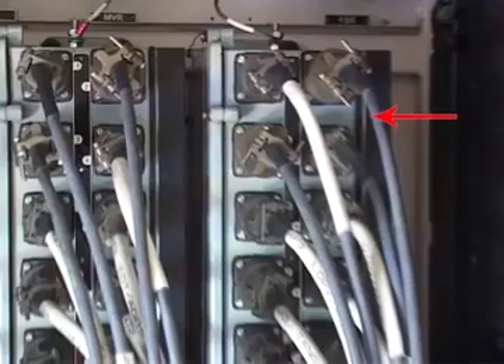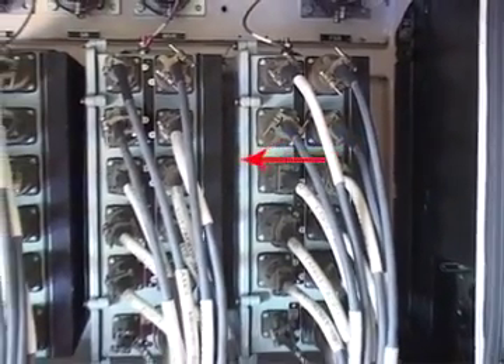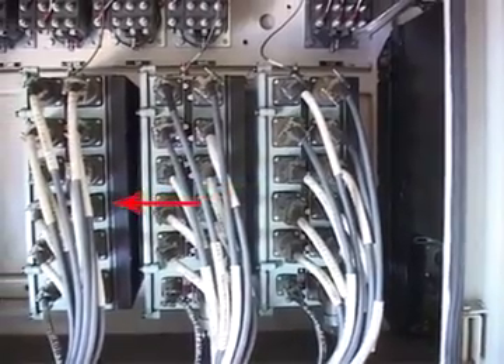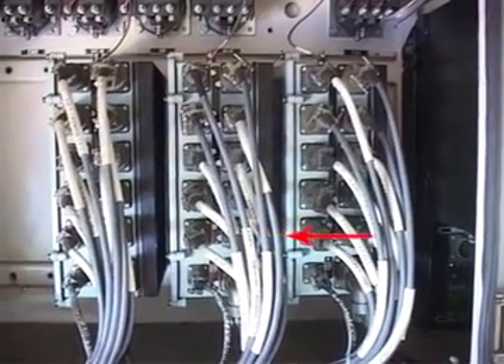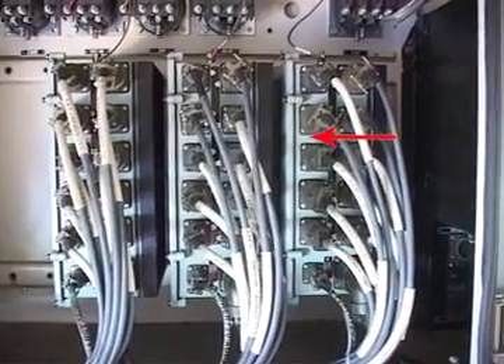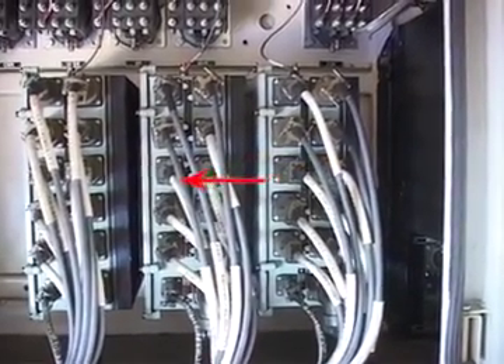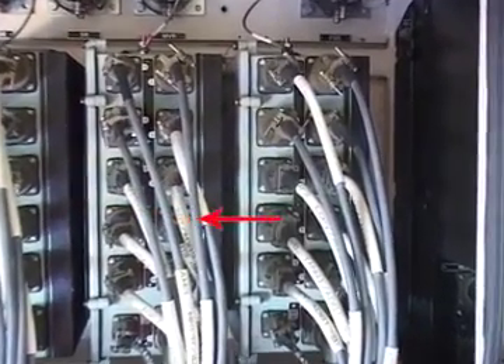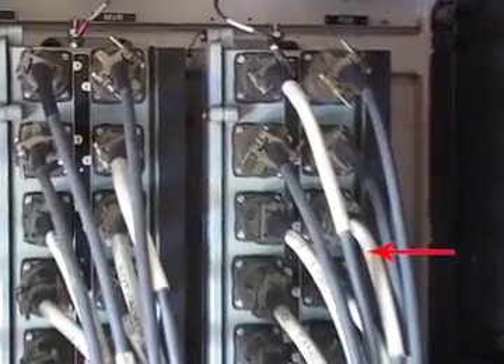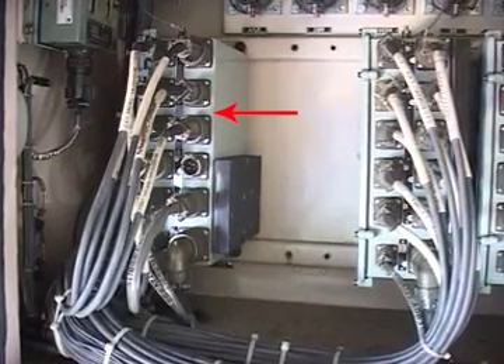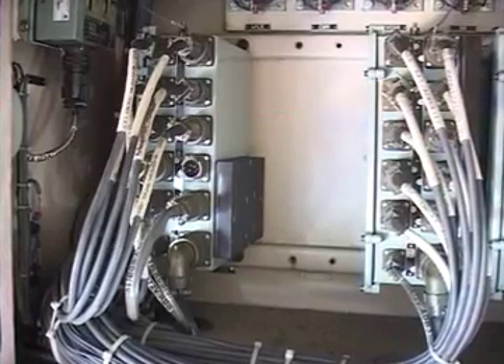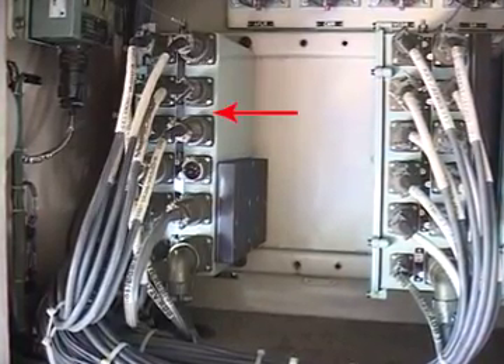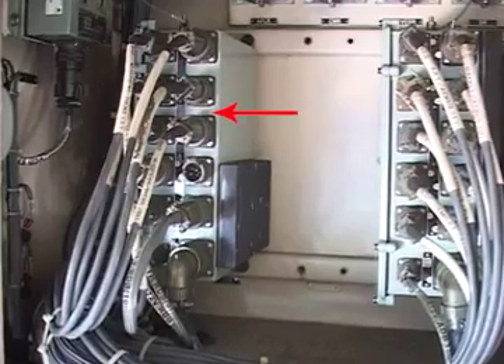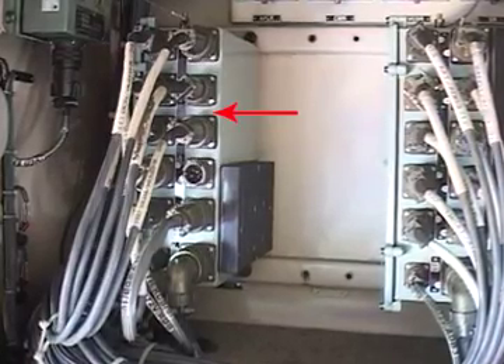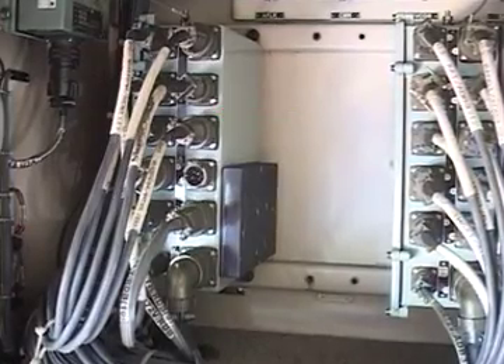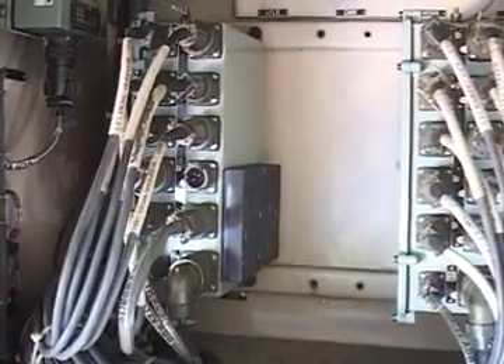Analog distribution box, ADB, MDB701. The analog distribution box provides regulated DC power to various sensors that are connected to the ADB. It also collects output signals from these sensors and transmits them to the main control unit. There are 4 ADBs per loco. RPM distribution box, RDB, MDB702. The RPM distribution box, RDB, supplies power to all the speed sensors connected to the RDB. It also collects speed signals from these sensors and transmits these signals to the main control unit.